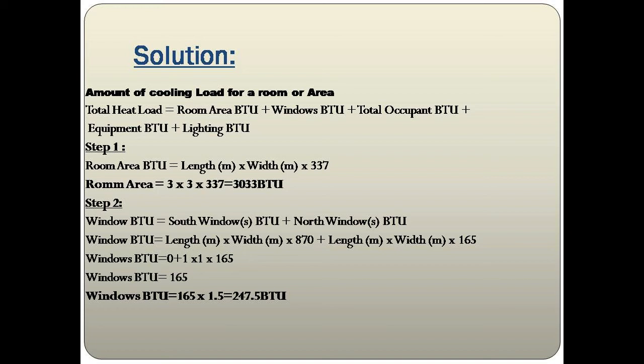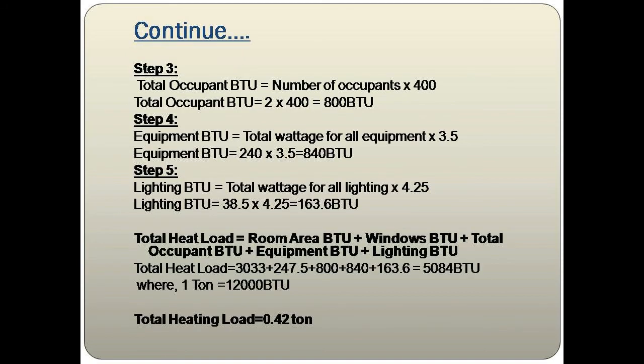Step 2 — There is no south-facing window, so south window BTU = 0. North window BTU = 1 × 1 × 165 = 165. Since there are no blinds, multiply by 1.5: total windows BTU = 165 × 1.5 = 247.5 BTU. Step 3 — Total Occupants BTU = number of people × 400 = 2 × 400 = 800 BTU.